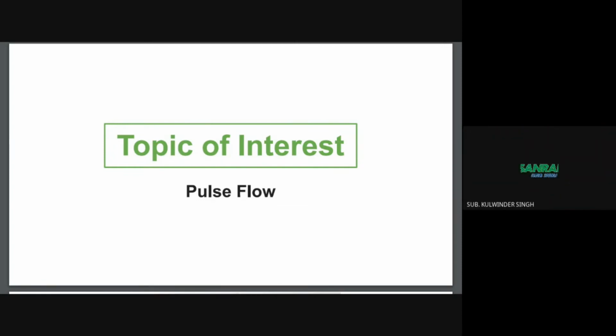Thanks, Maui. So today we will be talking about pulse mode used in the portable oxygen concentrators, a little different from the continuous flow used in the stationary oxygen concentrators. The working principle of both is the same, that is pressure swing adsorption. So no difference in the principle of working. Nearly all the components inside the machine are also the same. Nearly 1 or 2 extra parts are mounted on the PCB board, maybe the gas sensor or the oxygen conserving device instead of the oxygen sensor. So that is manipulated on the PCB.